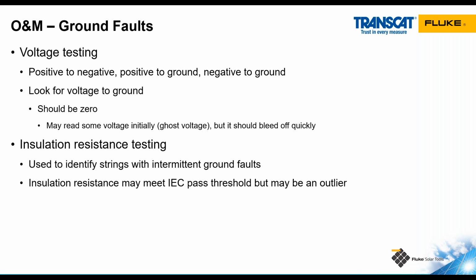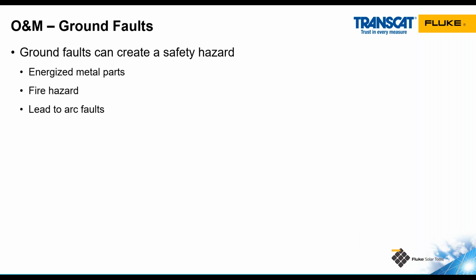I've run into this before where I was doing insulation resistance testing on a commercial rooftop system, and all the circuits were exceeding the resistance value of my meter, which was 2 giga ohms, except for one circuit, which was around 156 mega ohms. That is still well beyond the minimum required by that IEC standard, but significantly less than the other similar circuits. When I got out my string diagram and found the circuit, walked the array and did a visual inspection, I found an interconnection between two modules laying on the roof in a puddle. Not a good way to have your connector. So I took the connector out of the puddle, properly fixed it to the racking, let it dry off, and then retested it, and it exceeded the limit of my meter as well at 2 giga ohms. So that was a good change. Ground faults are a safety hazard.